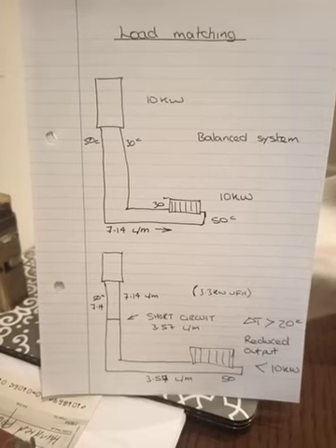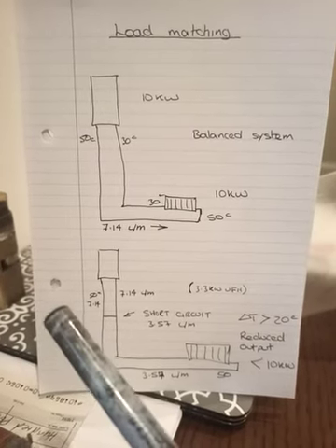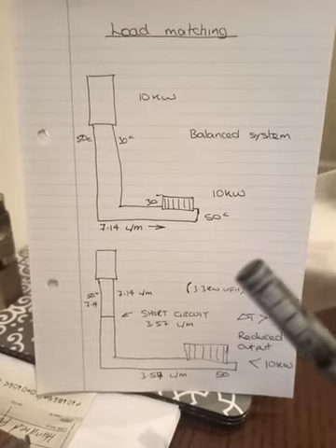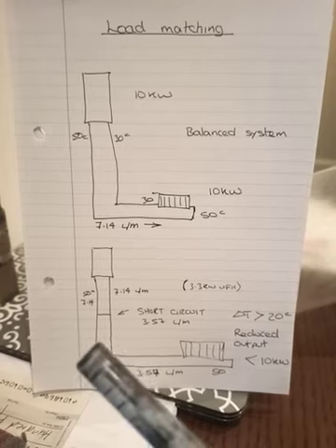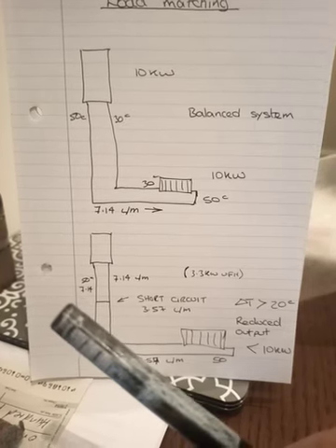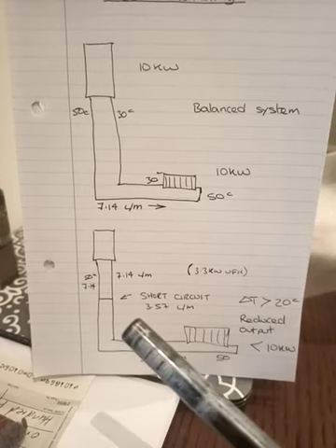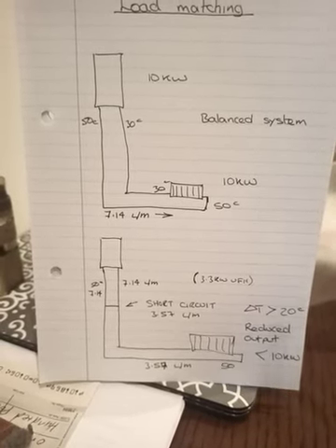So I hope that helps. I don't think we really need to draw in the underfloor heating circuit in here to demonstrate it any further. But to clarify the rule, basically no close coupled T's before a manifold when in parallel to a radiator circuit. Just one more thing, if you were to put a balancing valve into the underfloor heating circuit, which still allowed a bypass rate, all you're doing is reducing the severity of the bypass or the short circuit, and therefore you're reducing the impact of under output from the radiator circuit. Easy to get over, don't do it.